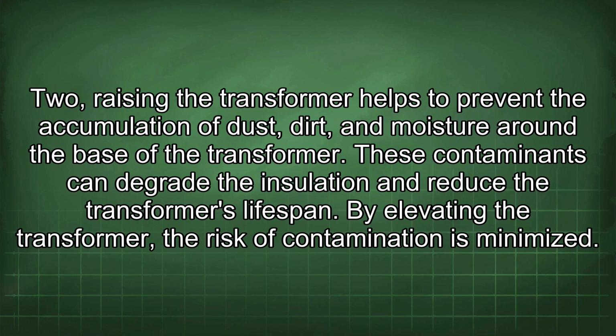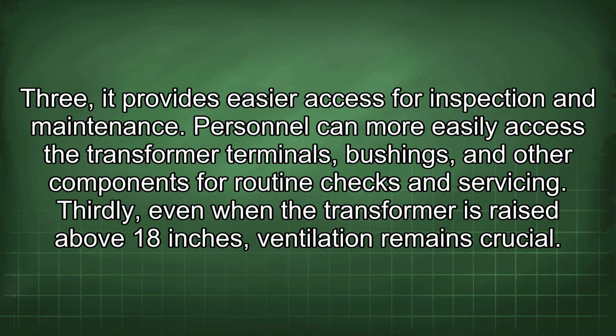heat. 2. Raising the transformer helps to prevent the accumulation of dust, dirt, and moisture around the base of the transformer. These contaminants can degrade the insulation and reduce the transformer's lifespan. By elevating the transformer, the risk of contamination is minimized. 3. It provides easier access for inspection and maintenance. Personnel can more easily access the transformer terminals, bushings, and other components for routine checks and servicing.